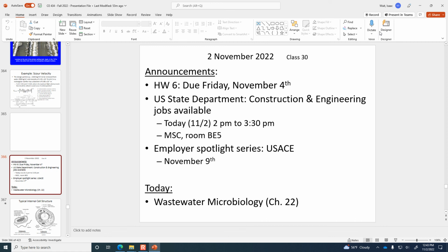But F to M is the food to microorganisms ratio. The food is generally fixed. That's the BOD that the microorganisms are going to be consuming. But the microorganism mass is what you can control through recirculating the settled sludge that you get at the secondary clarifier. So that's one of the important parameters mentioned in that video, where certain kinds of indicator organisms can mean that the F to M ratio is too high versus too low.